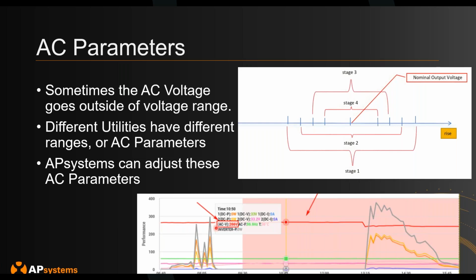There's going to be a range of acceptable numbers that the inverter can push power to, and a lot of times those ranges are actually set by the utilities. We also have default values for those parameters, so those ranges are set by default, but depending where you are and the grid quality, the voltage can exceed the ranges the microinverter is currently programmed at.